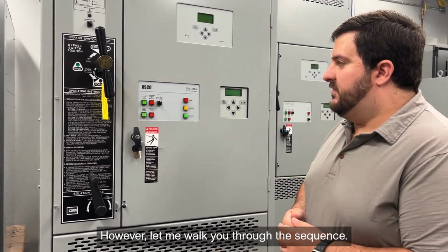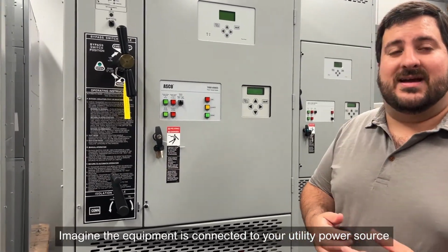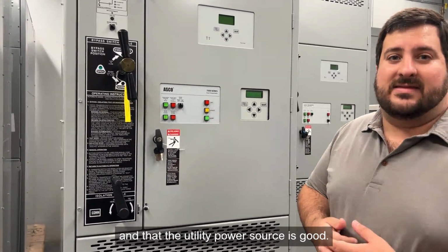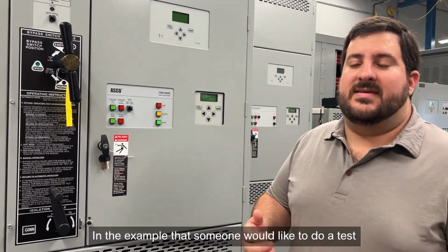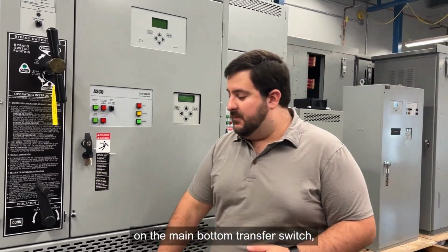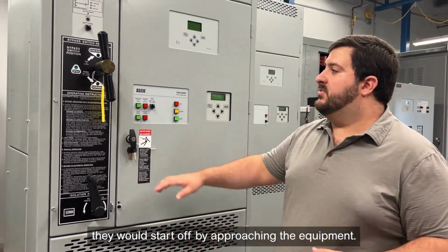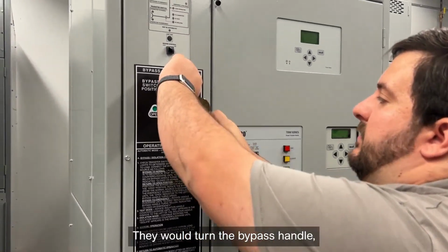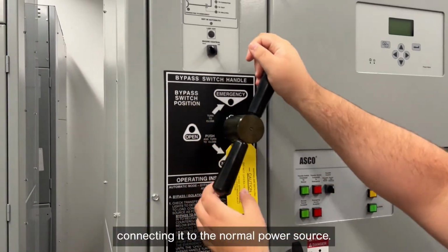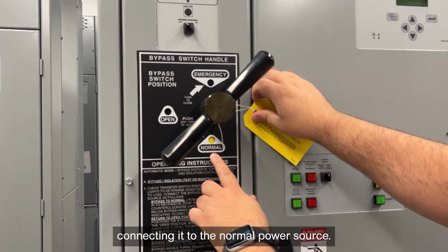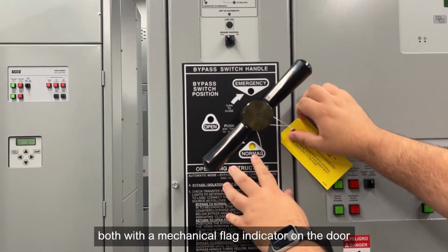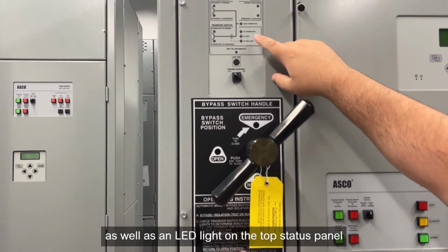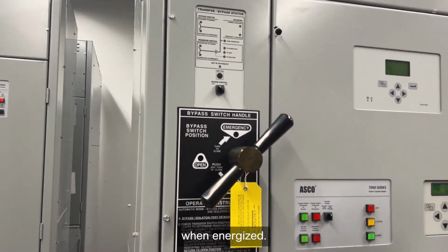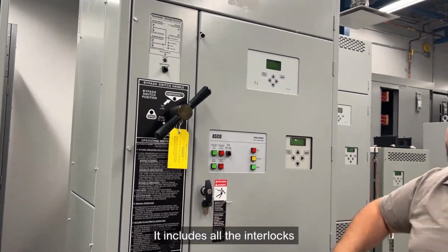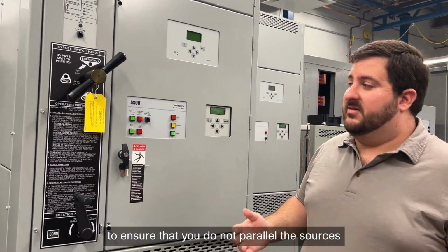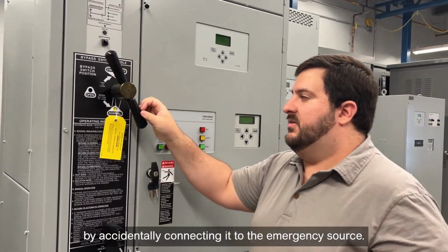This unit's de-energized for the purpose of this demonstration. However, let me walk you through the sequence. Imagine the equipment is connected to your utility power source and that the utility power source is good. In the example that someone would like to do a test on the main bottom transfer switch, they would start off by approaching the equipment. They would turn the bypass handle, connecting it to the normal power source. This will be represented both with a mechanical flag indicator on the door as well as an LED light on the top status panel when energized. It includes all the interlocks to ensure that you do not parallel the sources by accidentally connecting it to the emergency source.